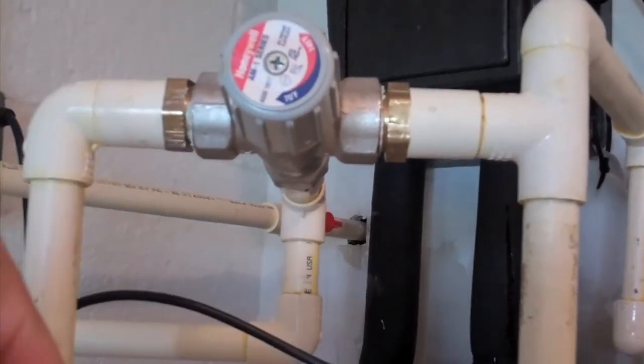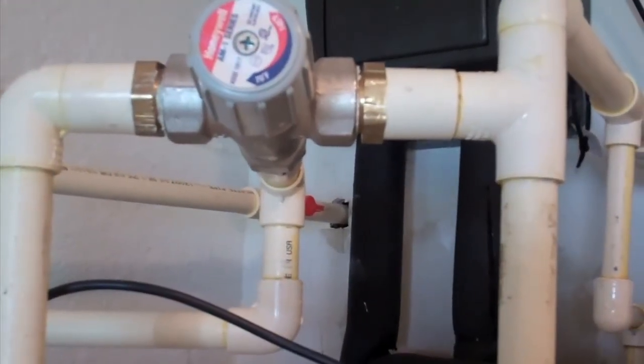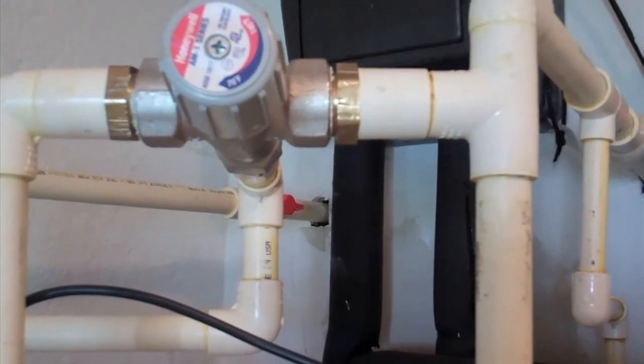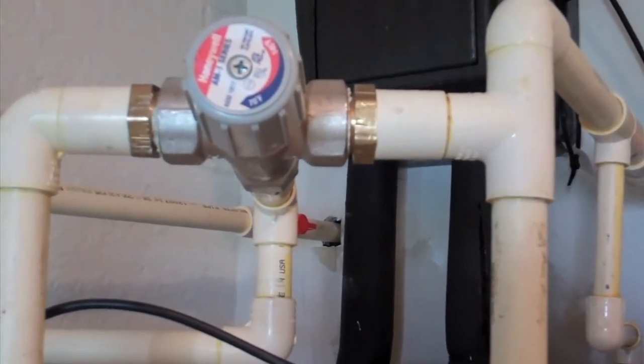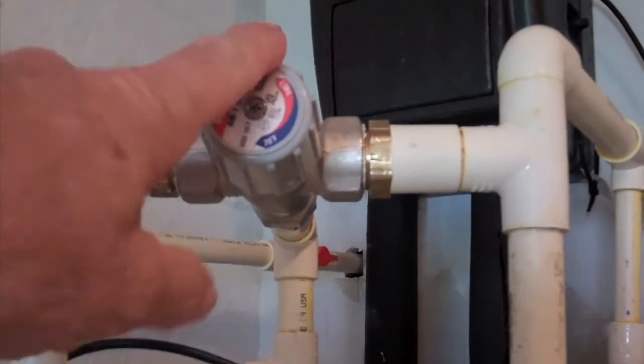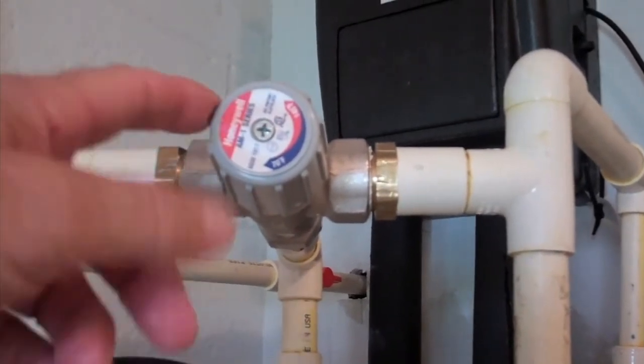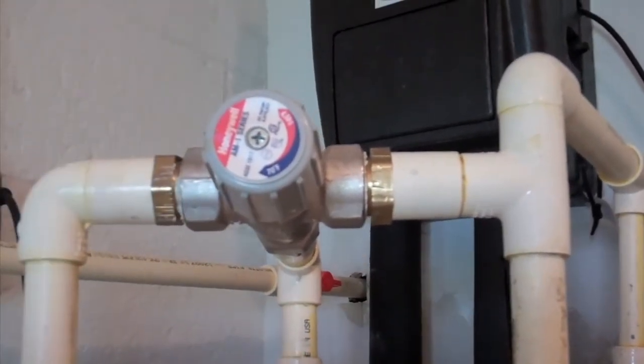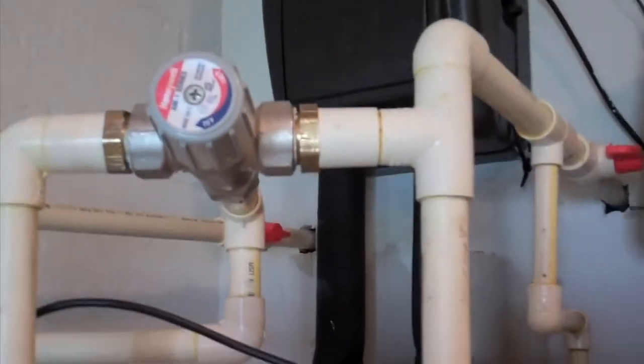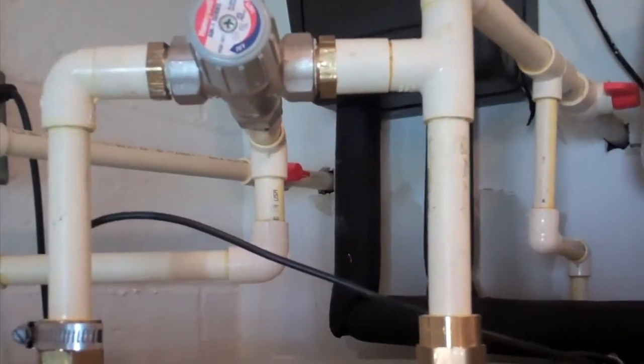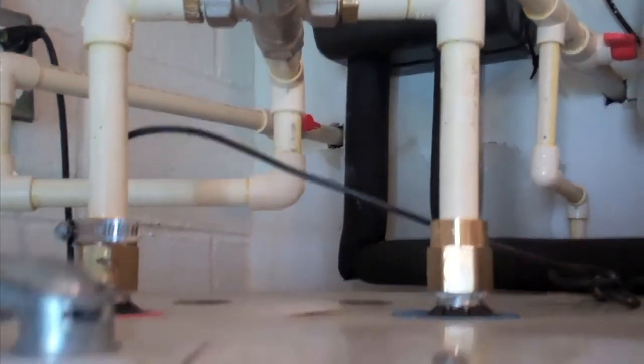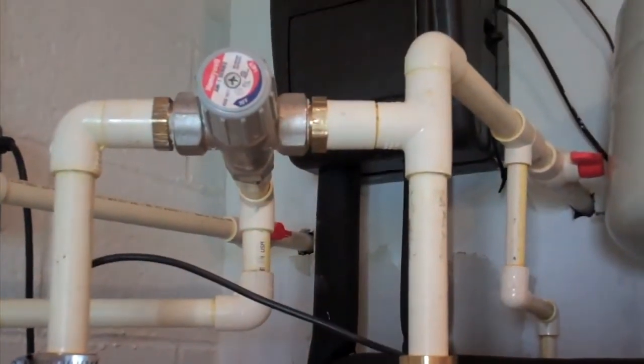The solar tank could get maybe as high as 140 degrees on bright sunny days, and we don't want that hot of water going into the house. So these are usually set to anywhere from 115 degrees plus or minus 5 degrees. And that's the tank inside of the solar hot water tank. Let's go take a look at the radiant flooring in the house.